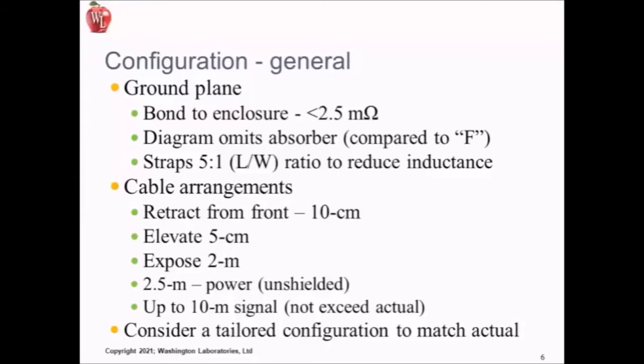So you consider a tailored configuration to match the actual, and tailoring is an important concept in those standard testing. You have to understand the operating environment. You've got to understand how the device is configured. And often when you're going into negotiations with a customer or a procurement agency, it's recommended that you keep tailoring in mind because you don't want to over-test or under-test. But getting that all worked out in the beginning can eliminate a lot of concerns during the actual test.